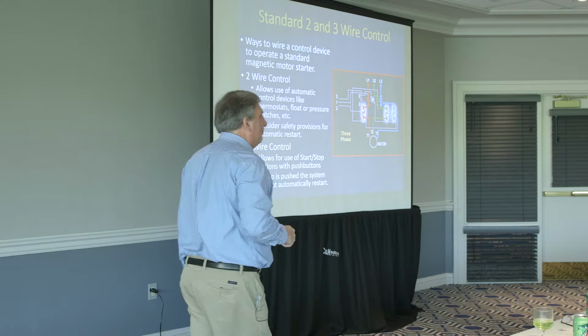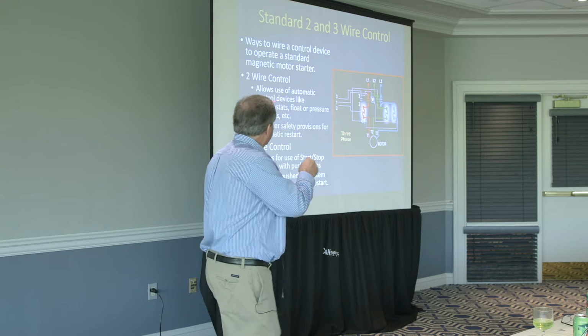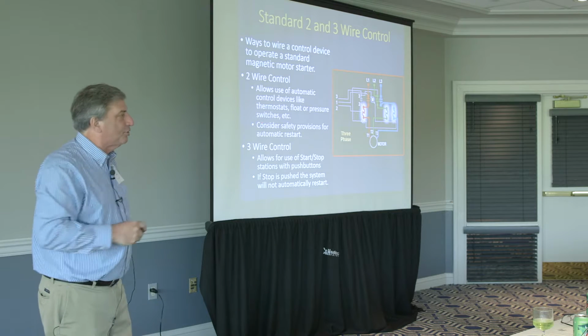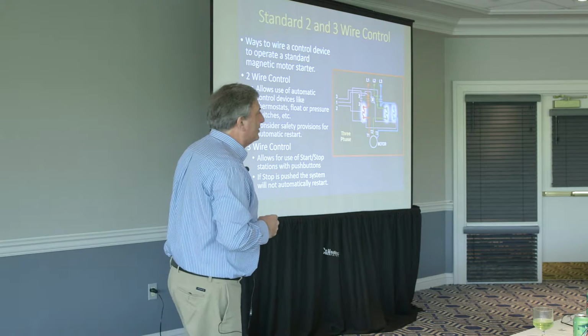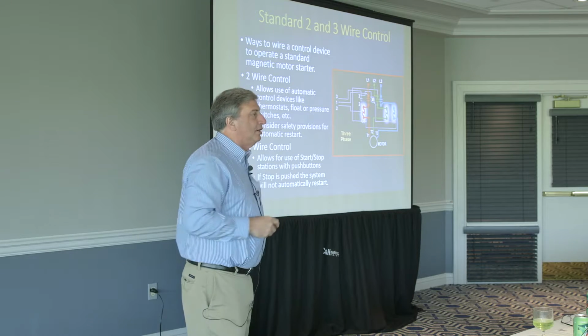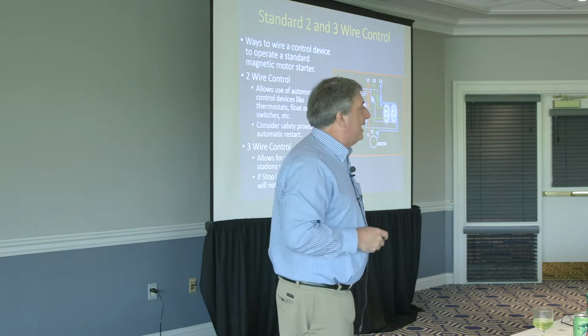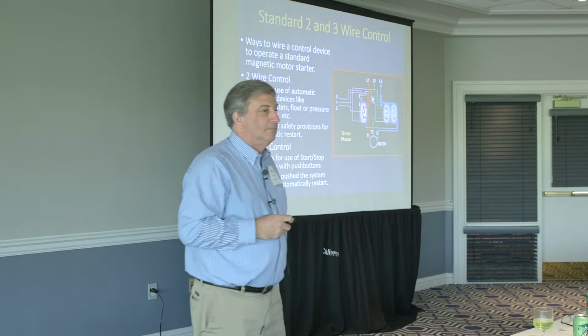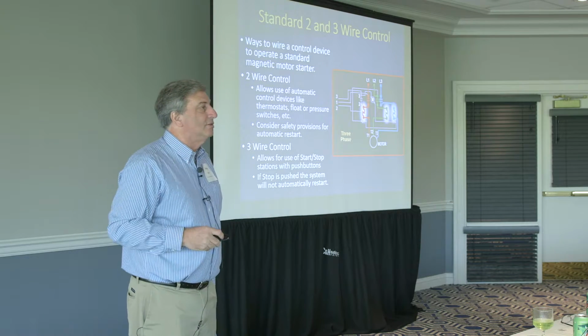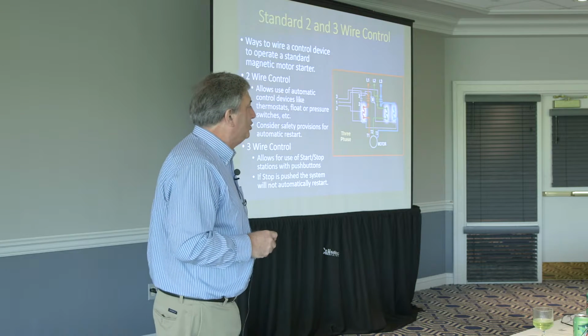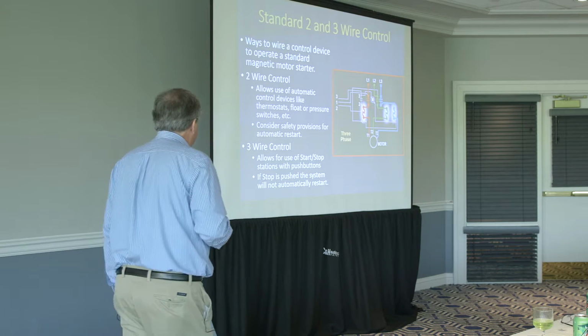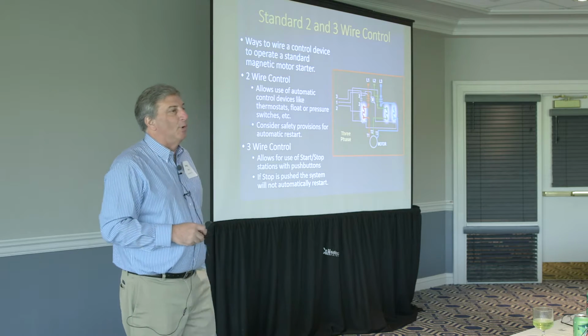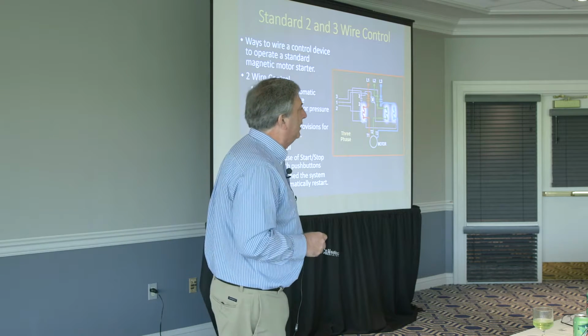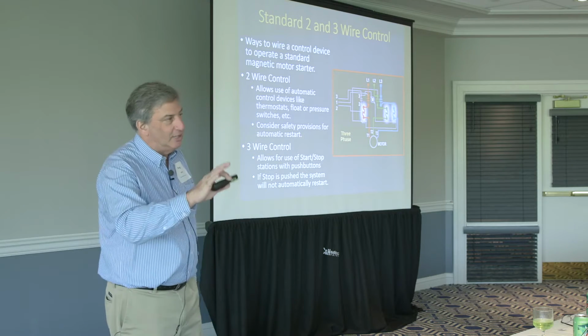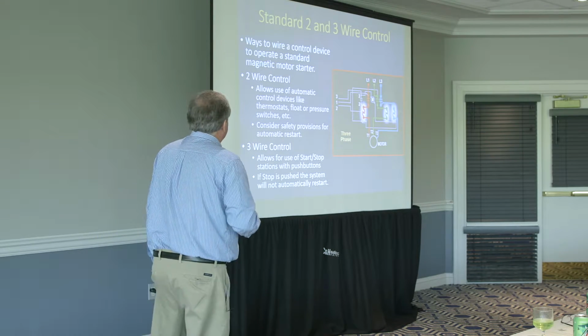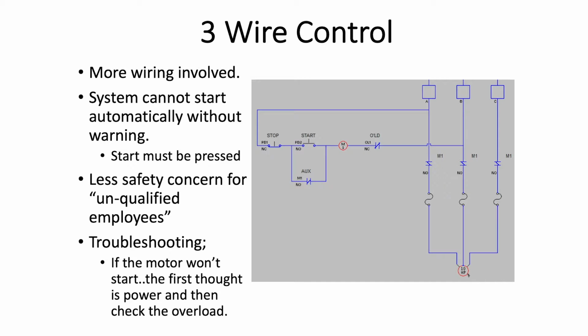It's got to be the start button pushed again. But in that 2-wire control with the thermostat, a float switch, a pressure switch, if that overload trips out and the contacts there are still closed and it's an automatic reset, it's coming right back on. It might overload again in 10 minutes, trip off again, but we've got that issue. So I've seen places where things broke down and people weren't trained to understand that it could come back automatically. There was no signing to say this machine could start automatically, etc., etc. Those are all conditions you see out there where somebody screwed up.